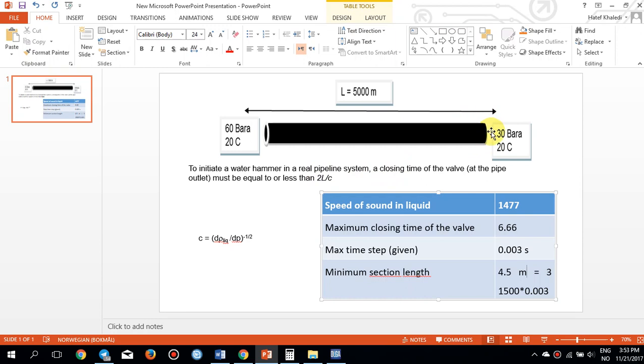In order to initiate a water hammer in a real pipeline system, the closing time of the valve — located right at the end of the pipeline — must be equal to or less than 2L over C, where L is the length of the pipe and C is the speed of pressure propagation inside the pipeline. Imagine you are closing a valve at time zero and the pressure starts to propagate back upstream.